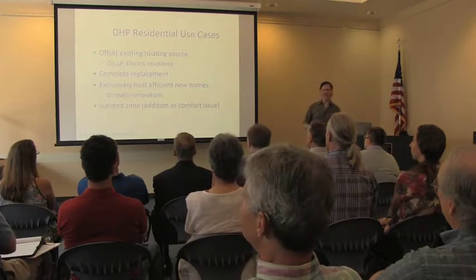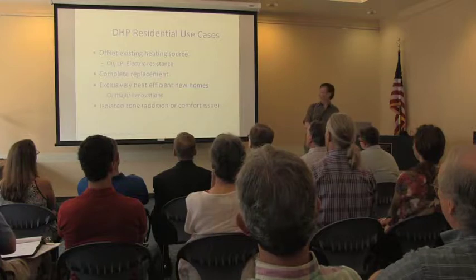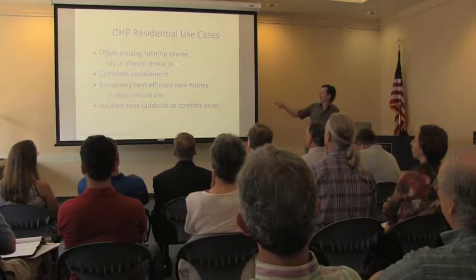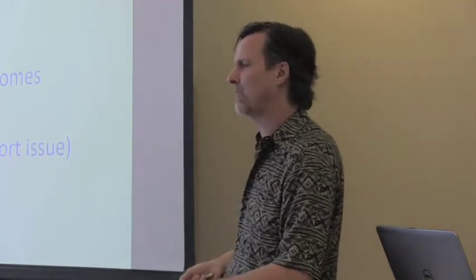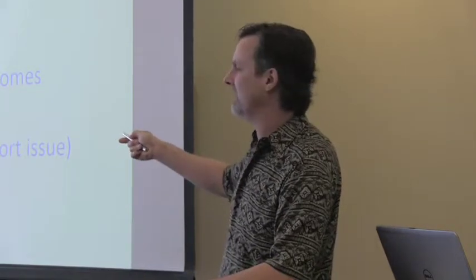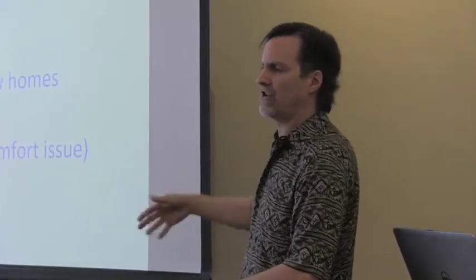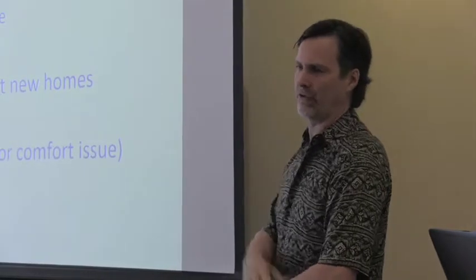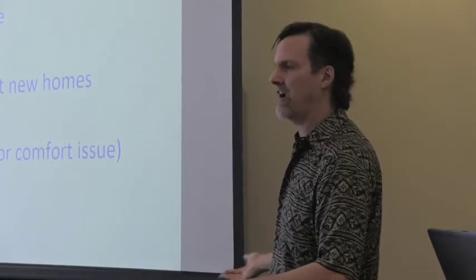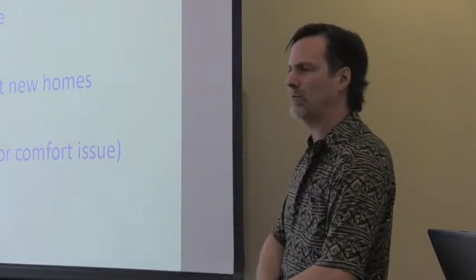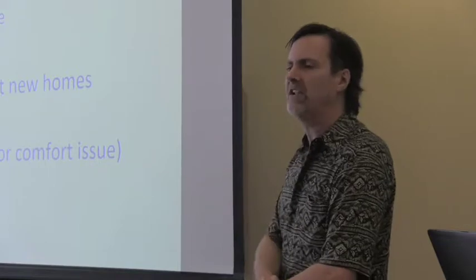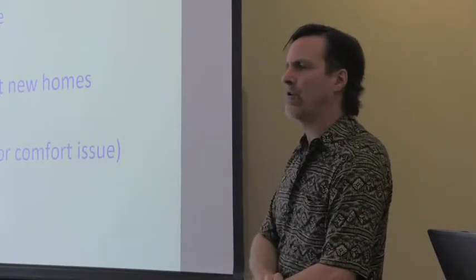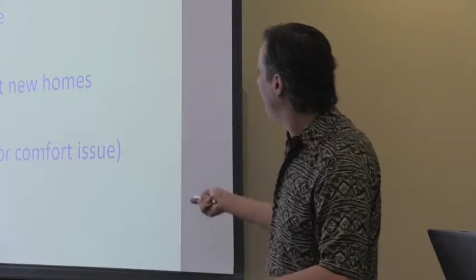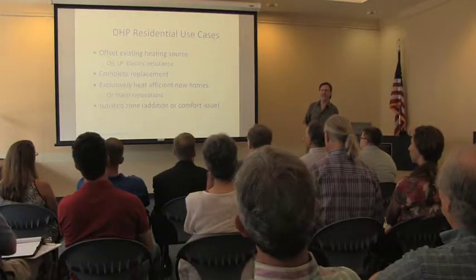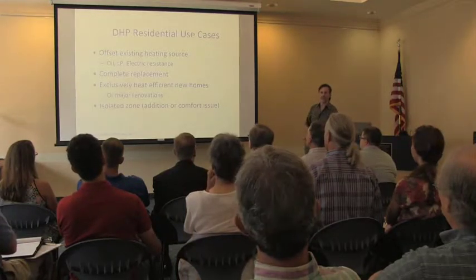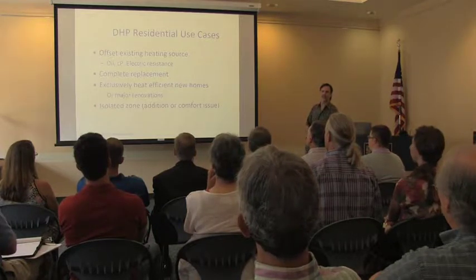There are a few standard applications in which we find these air source heat pumps are being used. And I say DHP for ductless heat pump because that's what most of it has been. But I'm, again, not limiting it to just ductless. Oftentimes we put in a single zone or a couple of zones to offset an existing heating source. And the point is not necessarily to heat the entire house 100% of the year, because you're leaving the existing heating system in place and that can handle peak cold periods. So you don't have to worry quite so much about whether you have enough heating capacity to heat the whole house. And for existing homes, this can actually end up being a very, very efficient and cost-effective way to reduce your use of LP gas, oil, or electric resistance heating.